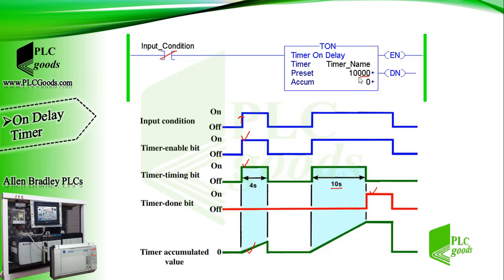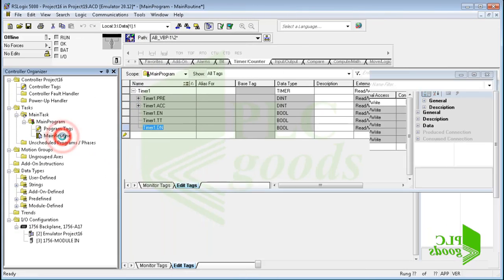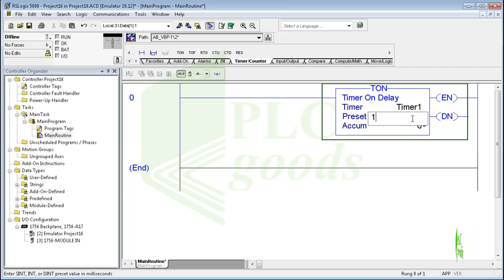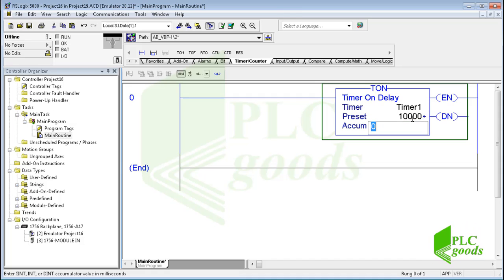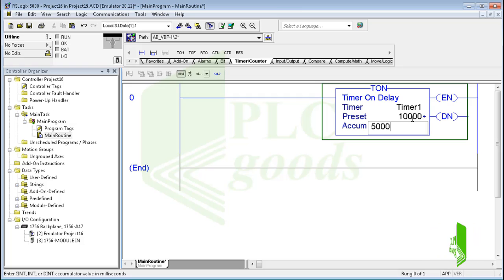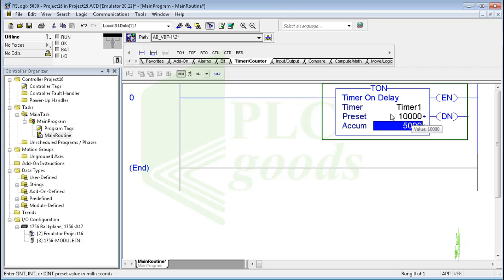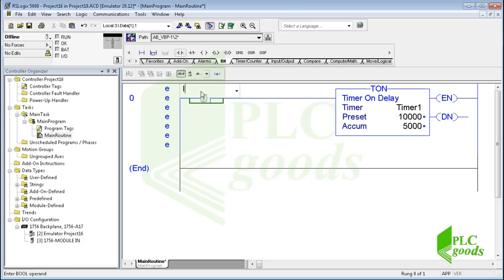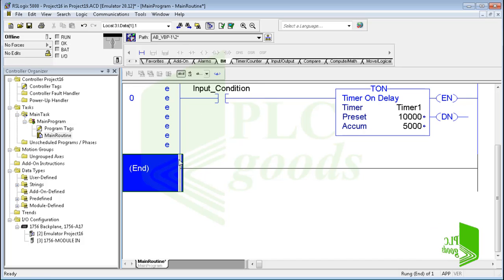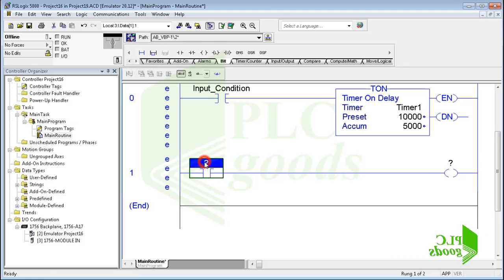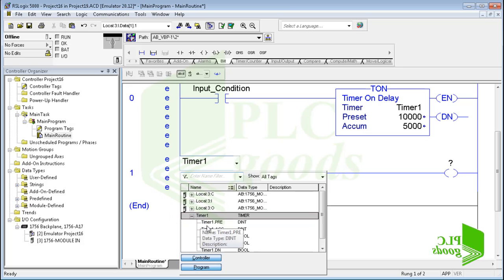Note that the time must be entered in milliseconds — as you know, 10 seconds is equivalent to 10,000 milliseconds. Let's enter 10,000 milliseconds as the preset value. Normally zero will be entered for the accumulator value; if I enter another value when the program is downloaded, this value will be in the timer for the first scan cycle. Note that if the timer is not enabled for the first scan cycle, the accumulator value will be set back to zero. Here I use the timer done bit to turn on an output after 10 seconds.